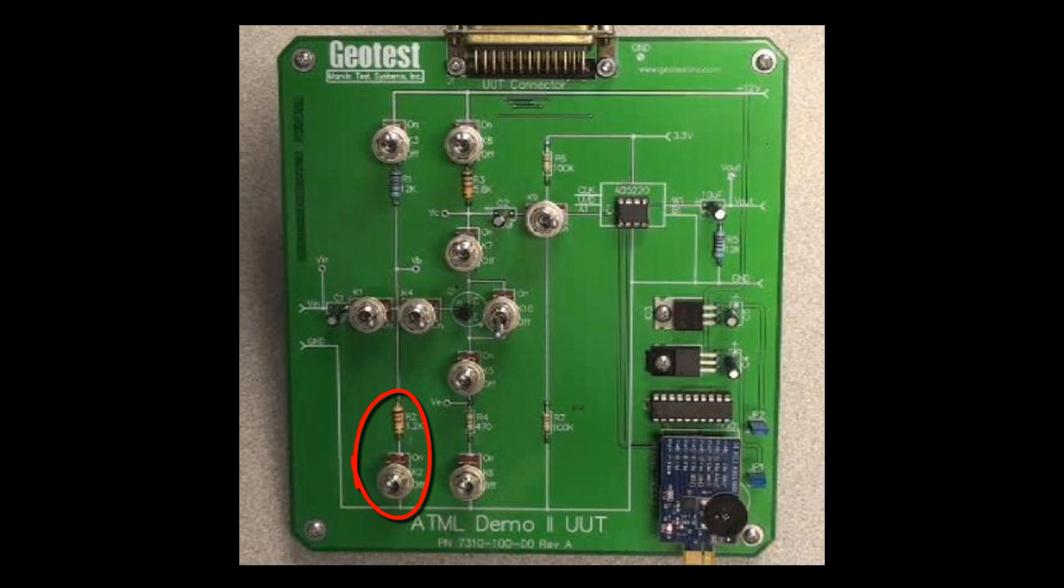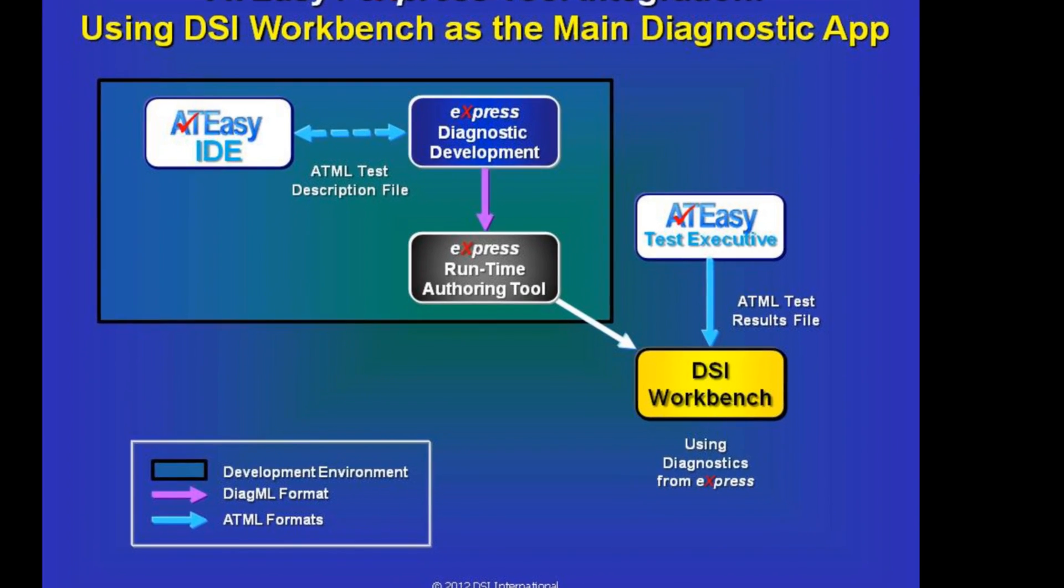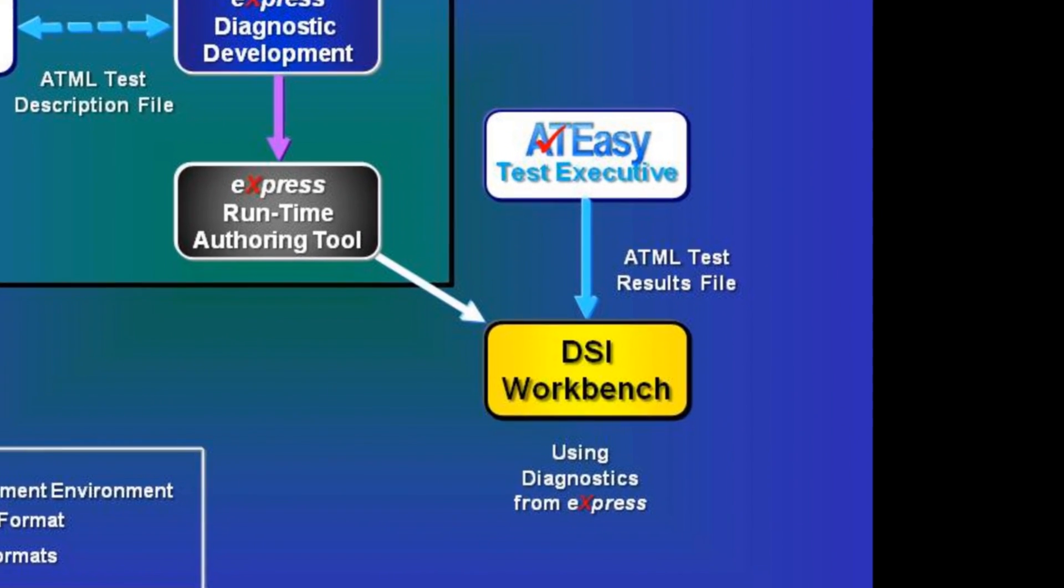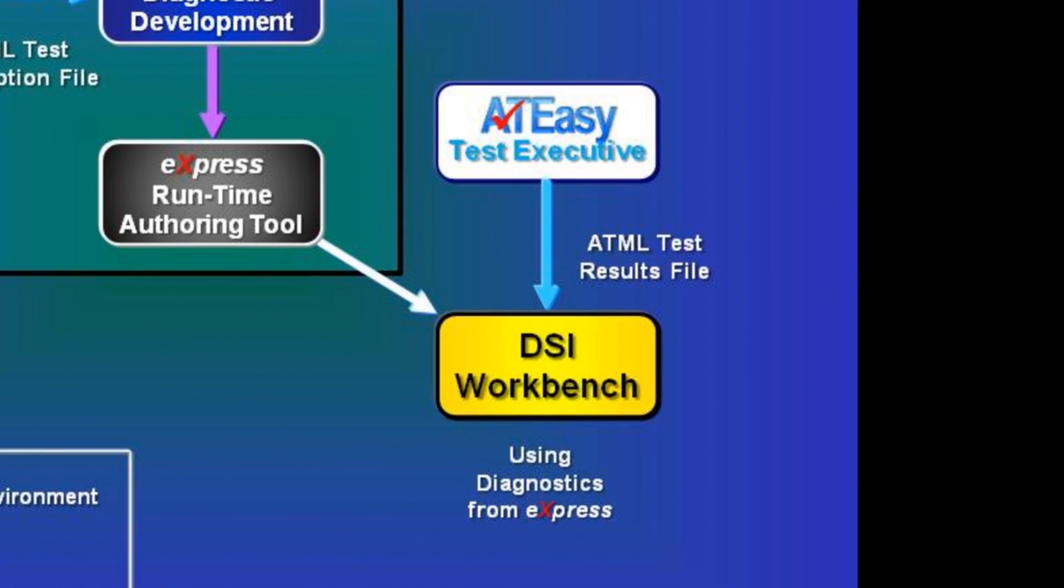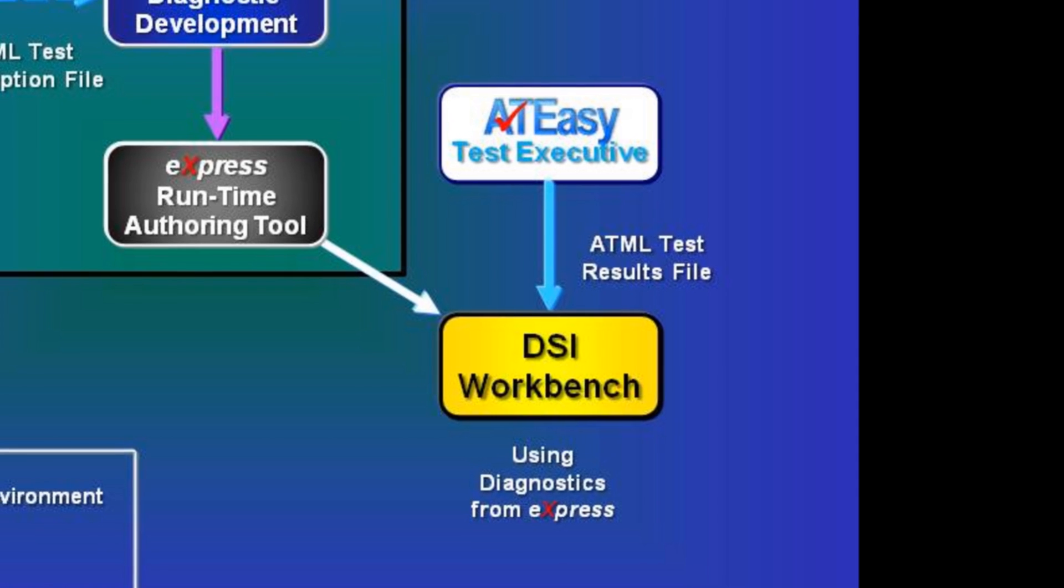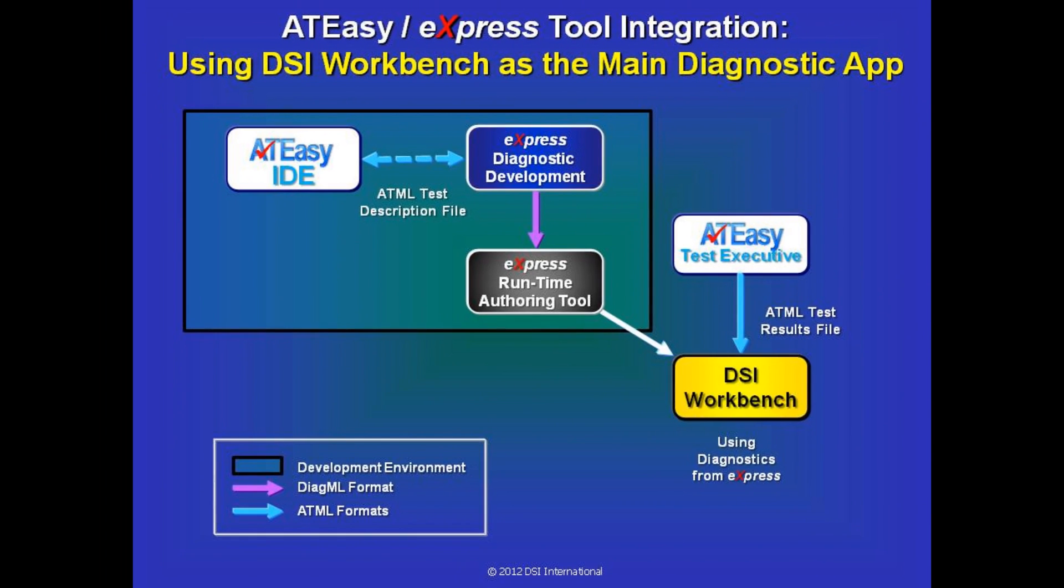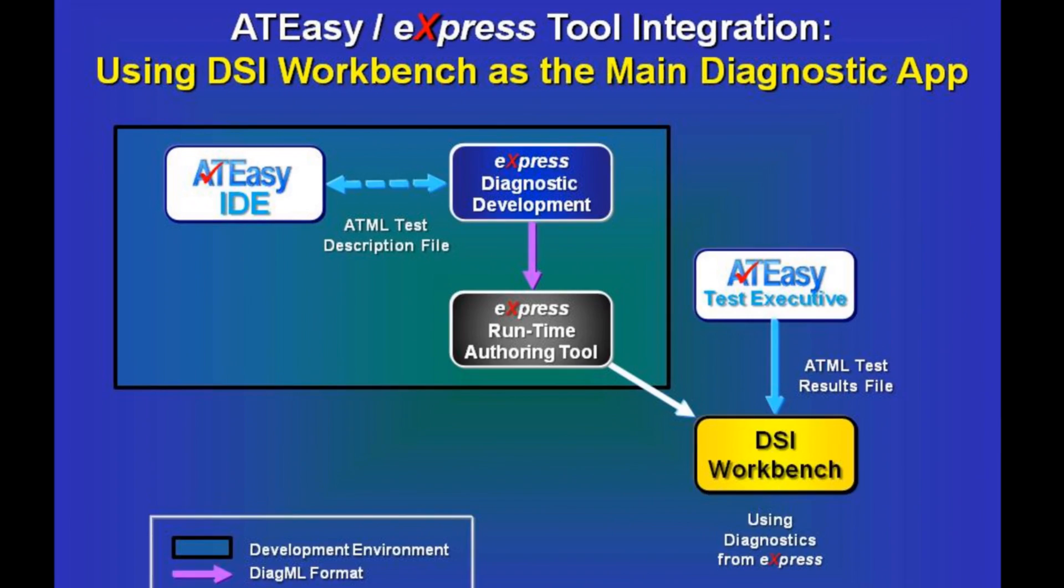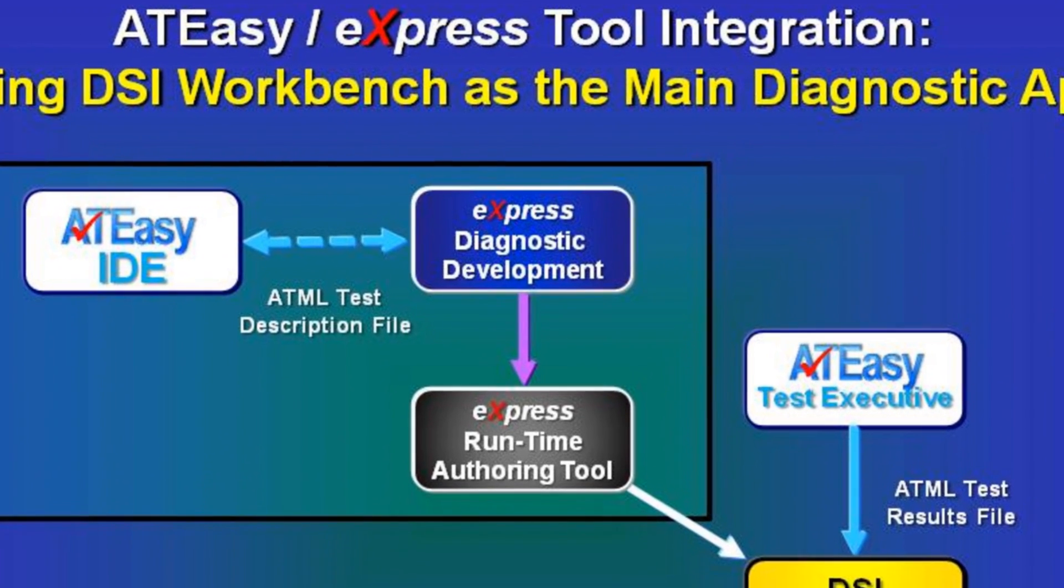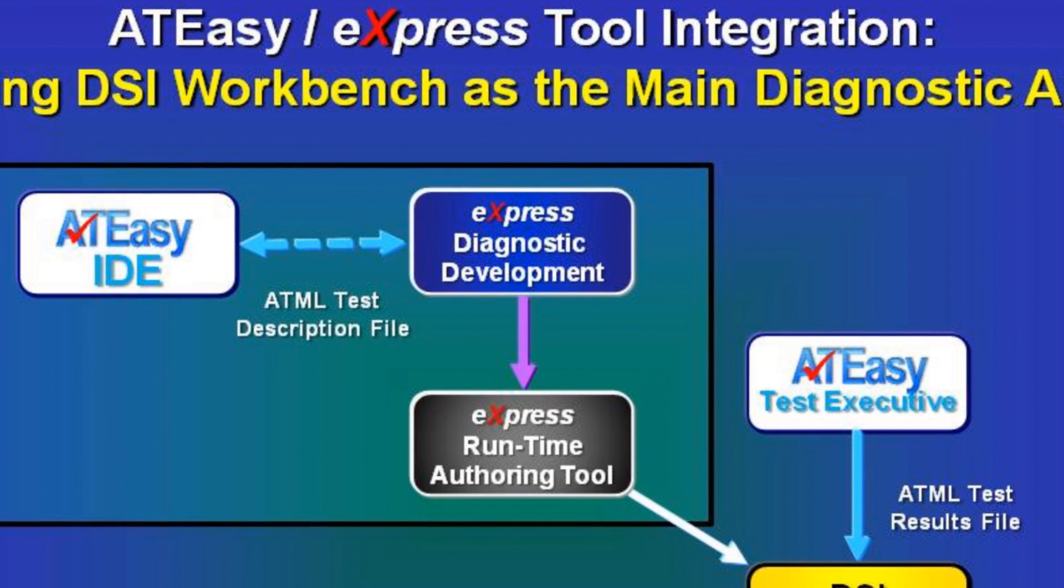The test executive works like this. If there is a failure, ATEasy will have generated an ATML test results file indicating exactly which test passed and which test failed during the execution of the test program. When DSI Workbench notices that the file has changed, it will then analyze these test results to determine which component or components have failed, using the diagnostic strategy that was developed up front using the eXpress software.